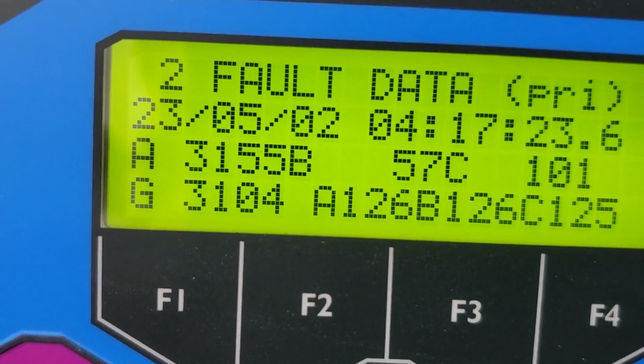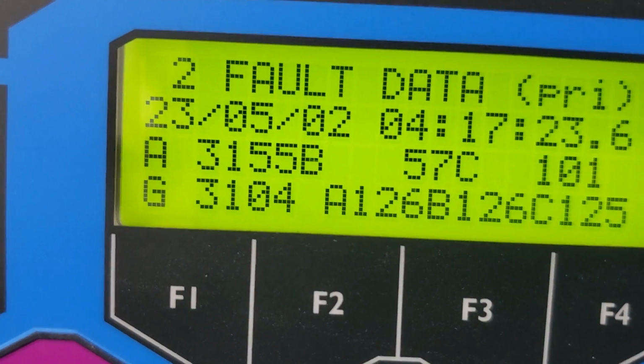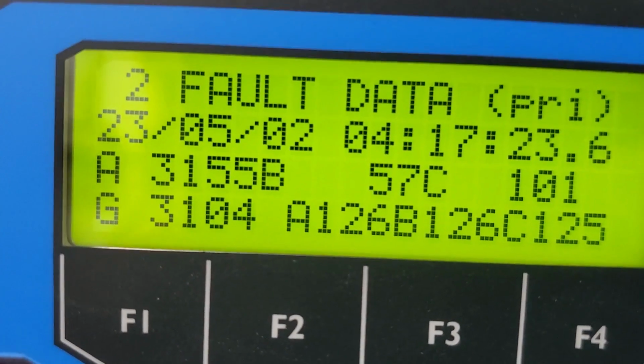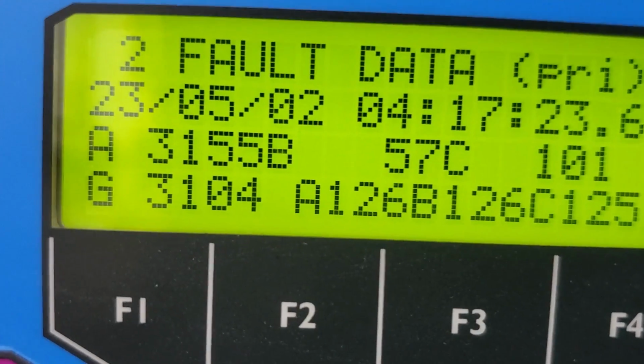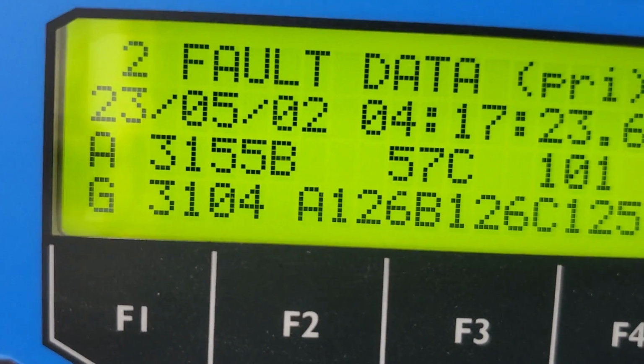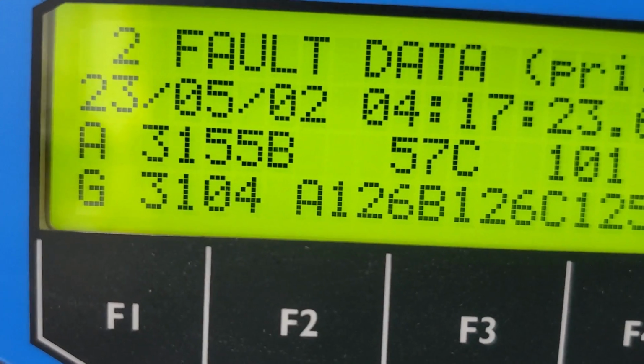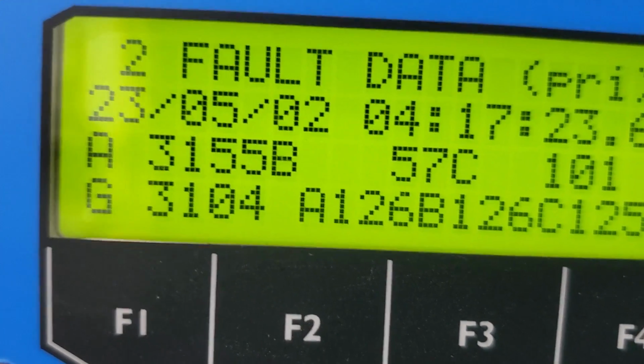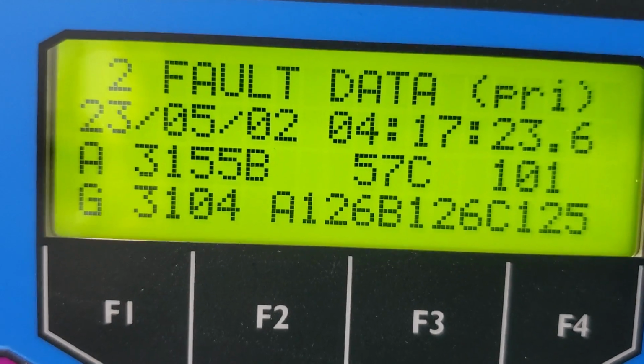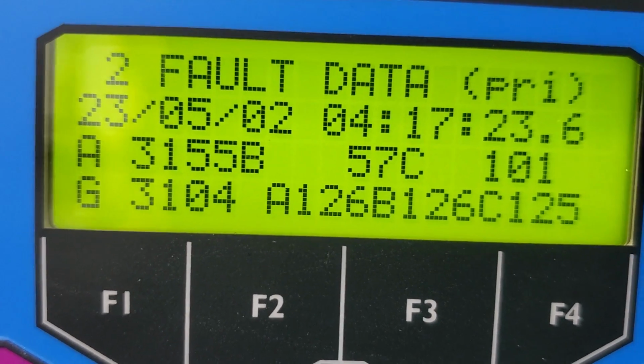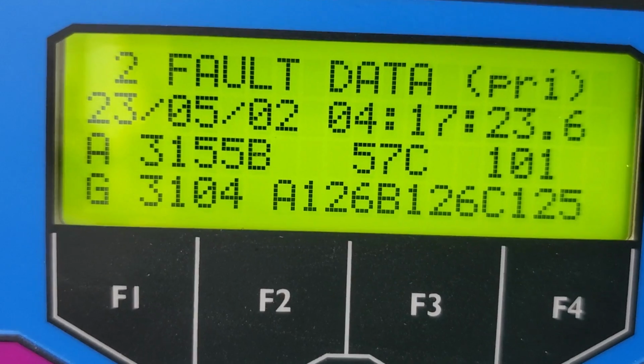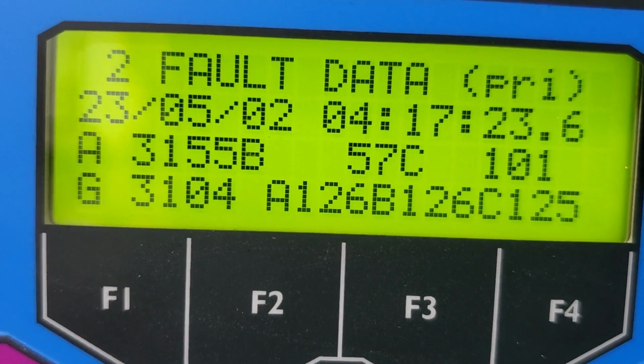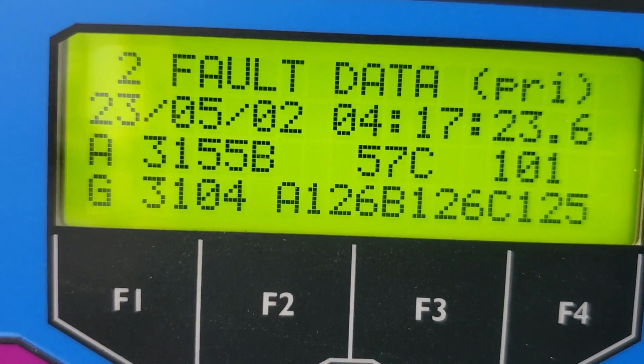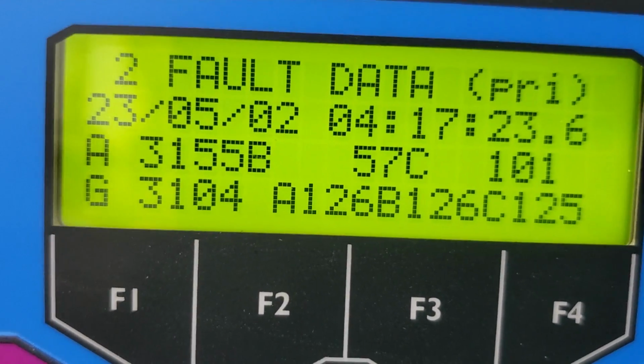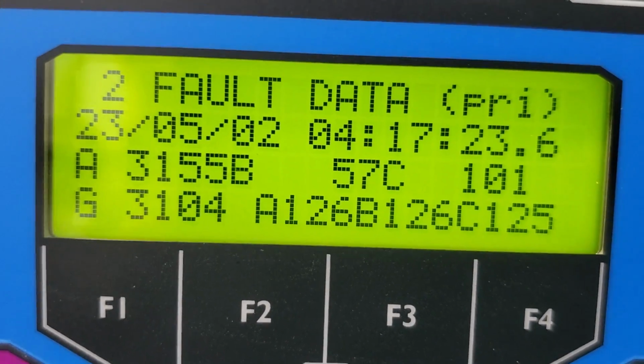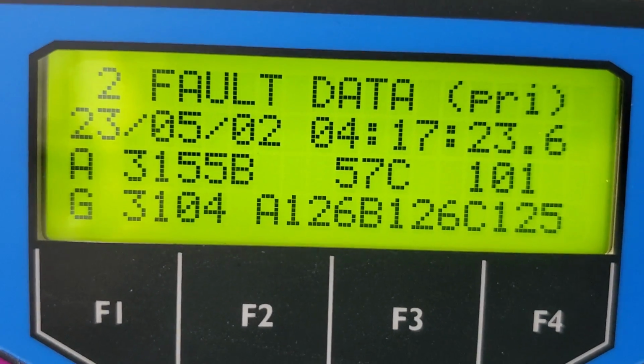So, if a customer reports, that's 2023 05 02, so May 2nd, 2023 at 4:17 a.m., 3155 amps on A phase and 3104 on ground. This is useful in a couple ways. One, sometimes the customer will write down and say, yes, the lights went off and on May 2nd at 4:15 a.m., along with some other dates. I can cross-reference that with the information on this recloser panel.